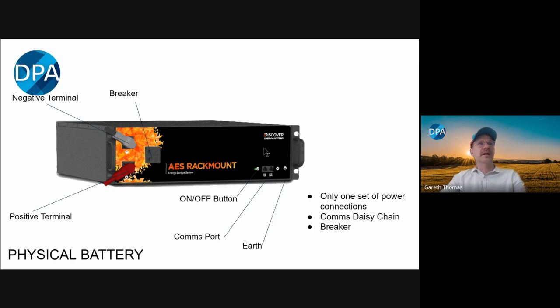These comms ports are used to daisy chain the batteries together and then go onto the Link 2 device, which I'll discuss in a moment. There's also a little earthing point here. It's important to notice there's only one set of connectors - unlike some other batteries which have a pair, which seems like a good idea, but now that the batteries are the size they are, you don't want to daisy chain them together because the currents are too large for the cables. You really need to take them back to an independent bus bar to manage all the currents correctly. Whereas some other batteries still have a pair of connectors on the front even though they've got quite large capacity, which is quite a compromised design, really.